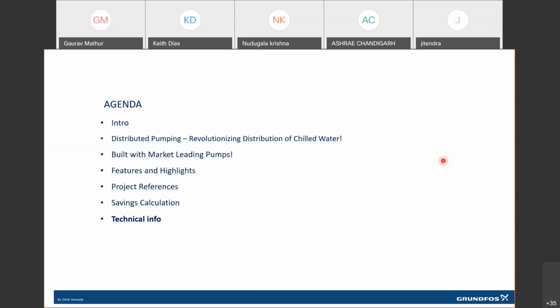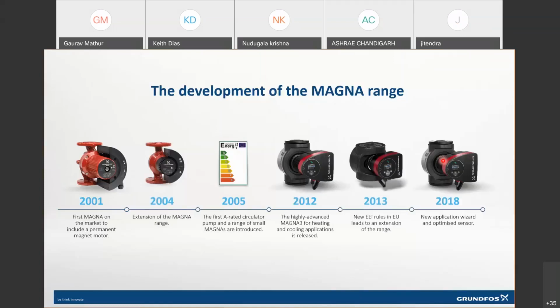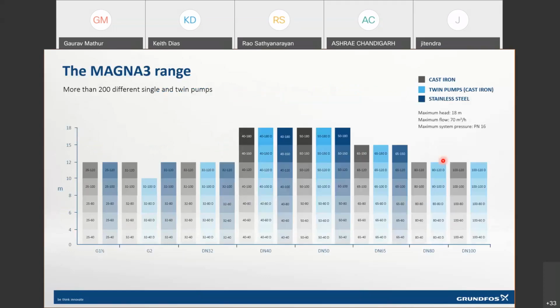The last but not the least is that the design which we are talking about, our circulators, is not something which has come up now, but it is a robust design which has developed on a platform over decades, and the pumps have been in operation for decades in various circulation applications in both heating and cooling. So it's a very wide and robust range which has evolved over a period of time, where we have brought a lot of intelligence and customer feedback into the design of the pump. So it's a very robust solution which we now have with the distributed pumping.